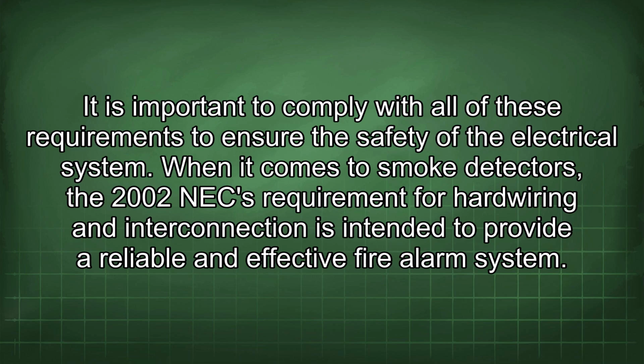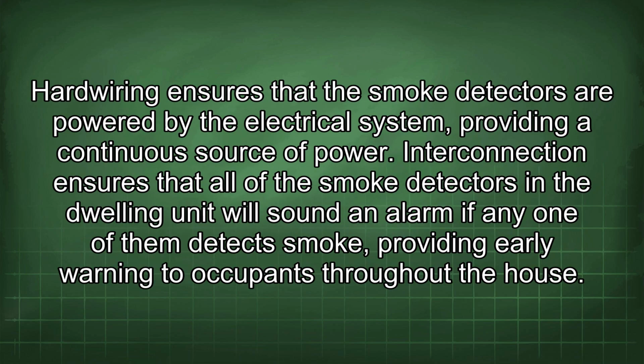system. When it comes to smoke detectors, the 2002 NEC requirement for hardwiring and interconnection is intended to provide a reliable and effective fire alarm system. Hardwiring ensures that the smoke detectors are powered by the electrical system, providing a continuous source of power. Interconnection ensures that all of the smoke detectors in the dwelling unit will sound an alarm if any one of them detects smoke, providing early warning to occupants throughout the house.